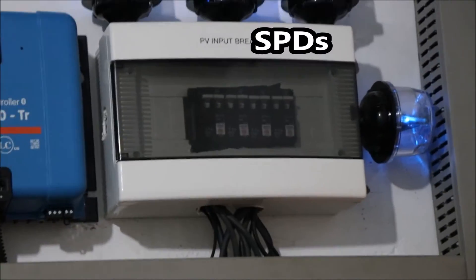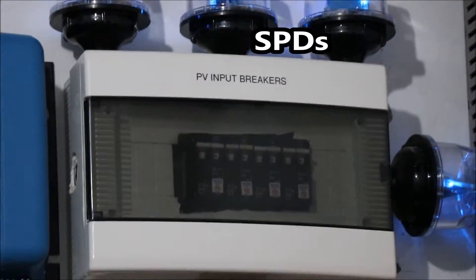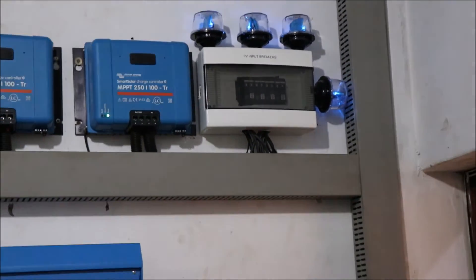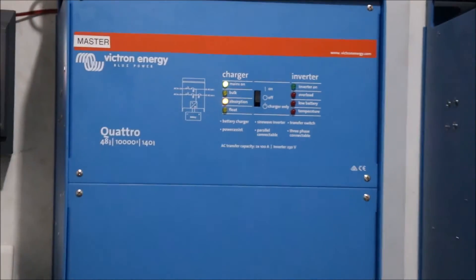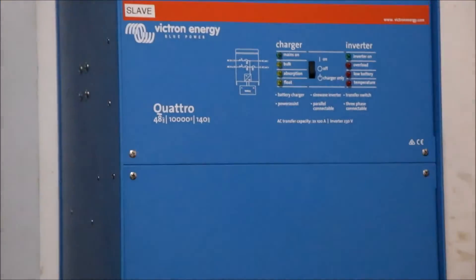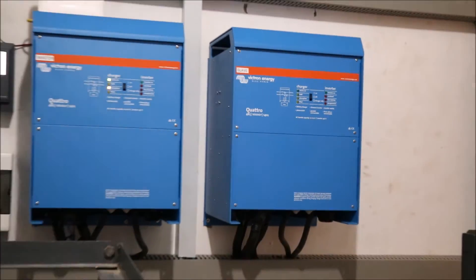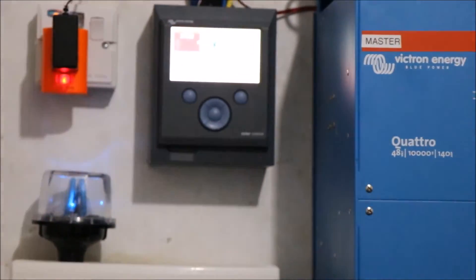Now, to the SPDs — these are the surge protection devices. The ones we have installed are Midnite surge protection devices, and we have both the AC and DC variants. The SPDs prevent transient overvoltage from reaching your equipment, and they are also responsible for diverting surges to alternative routes such as to the ground, thereby protecting your connected equipment.